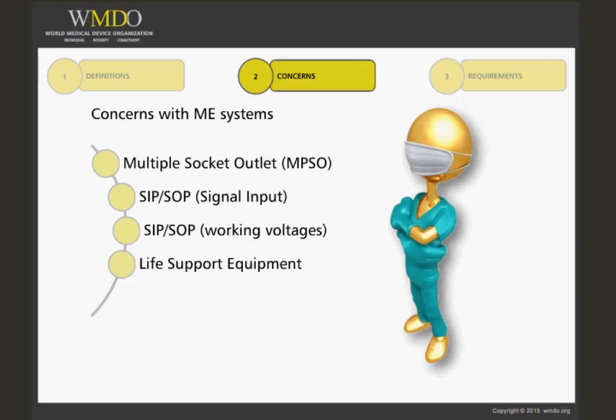The next concern has to do with life support equipment, since its function could be affected by electromagnetic compatibility, the interconnections, and proximity of other equipment, which must be taken into account. For example, if a computer is part of the system, the electromagnetic compatibility it emits and the conductive radiation must not affect the medical device in that system.